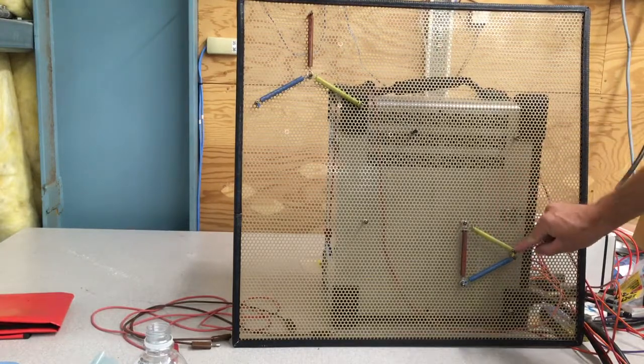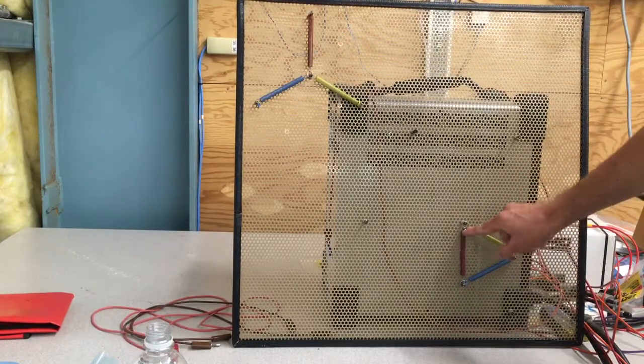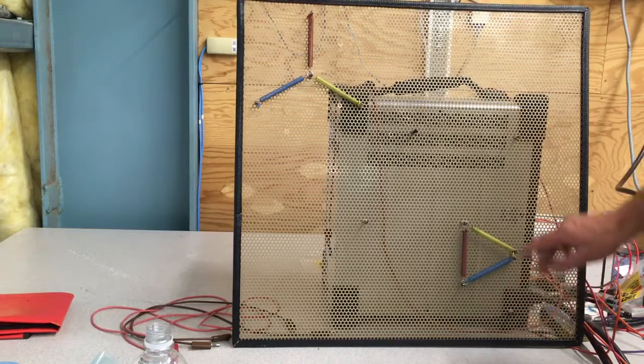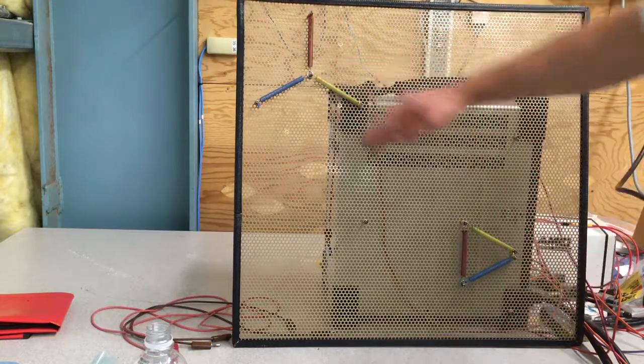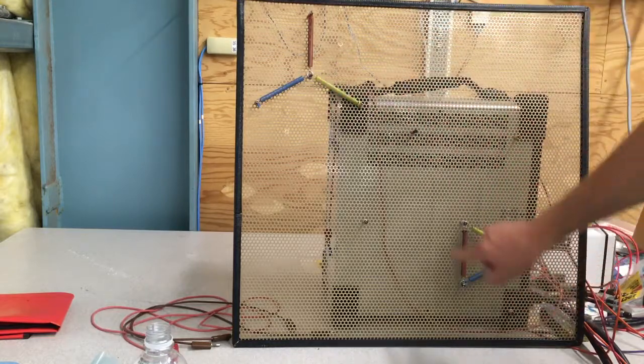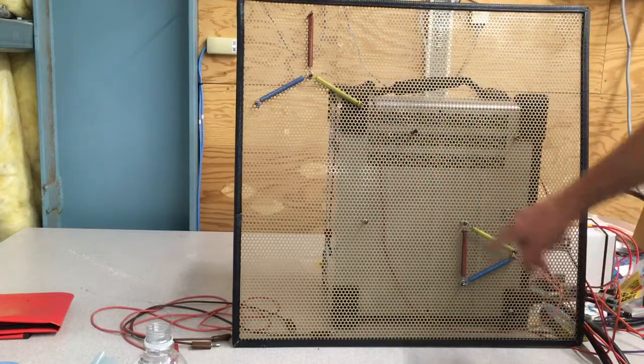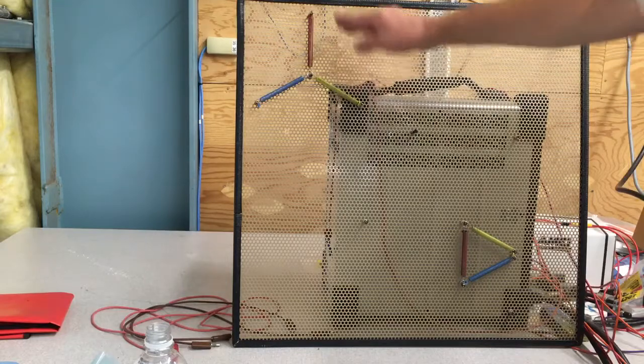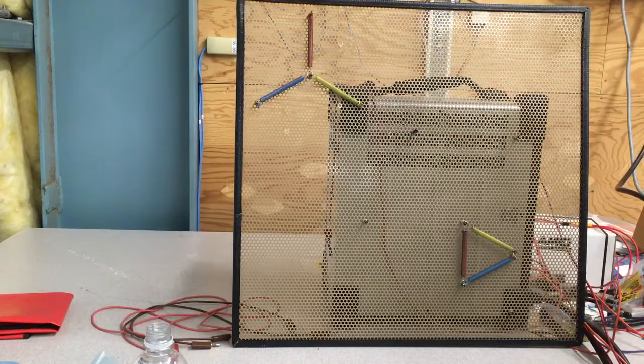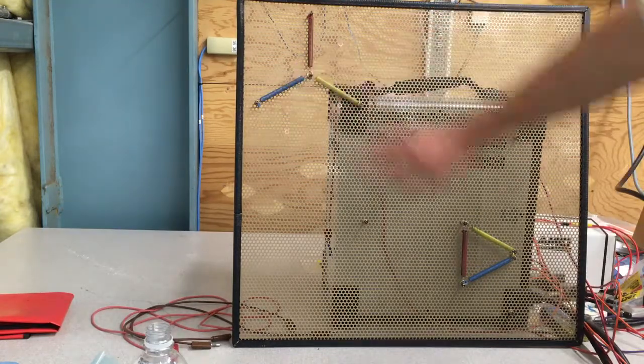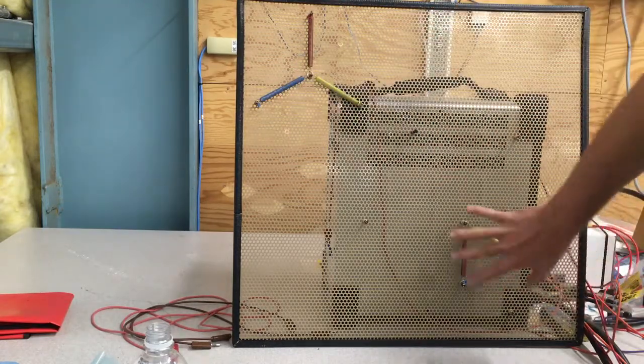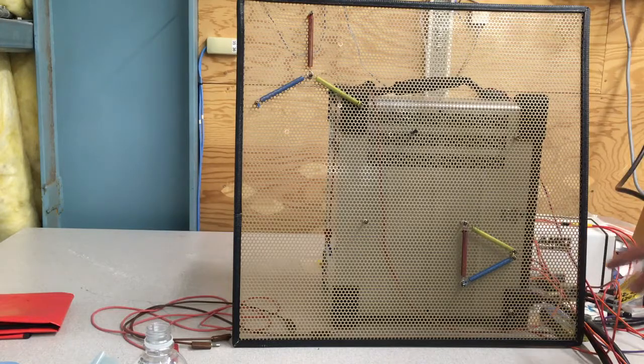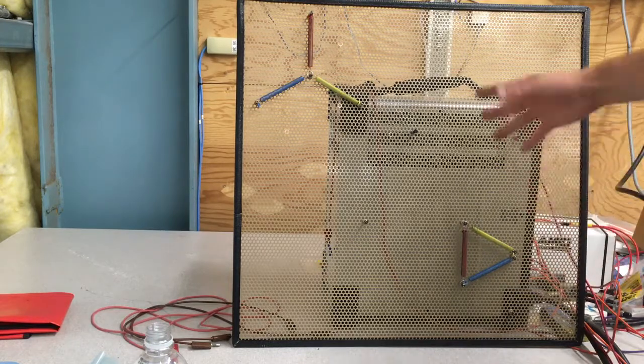It matches magnitude and angle as to what's going on here. No matter what goes on here, the same always has to happen here. The windings have to be the same magnitude and have to be the same angle, and that's why this works.